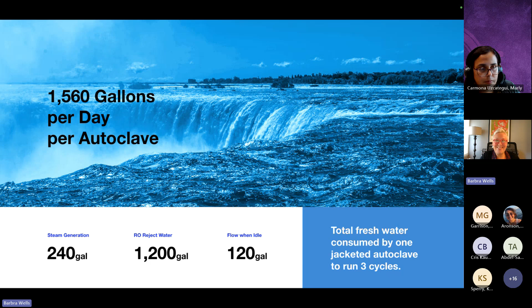But wait, there's more. Jacketed autoclaves continue to vent clean water even when they're idle. Across manufacturers, a typical rate is 5 gallons per hour. If we run that over a day, that gets you the 120 gallon figure. All of this translates to a cost of about $5,600 per autoclave per year, based on the average cost of water here in America. But who cares about the money? We need to save that clean water.